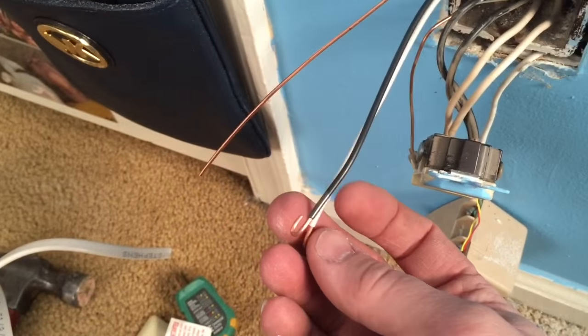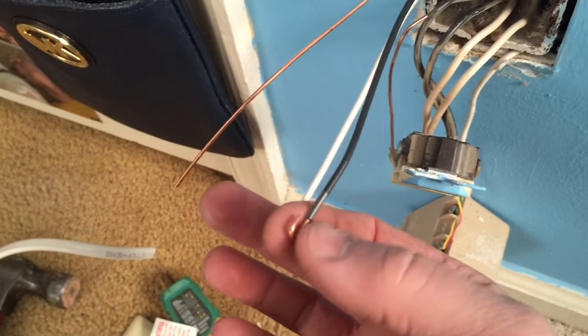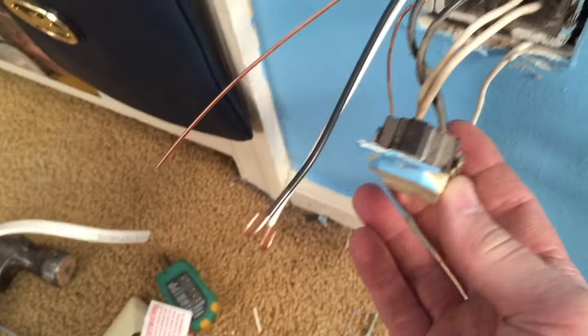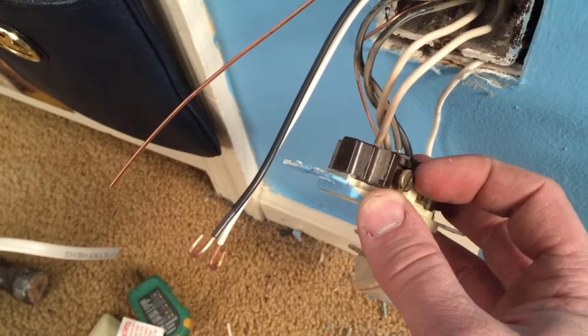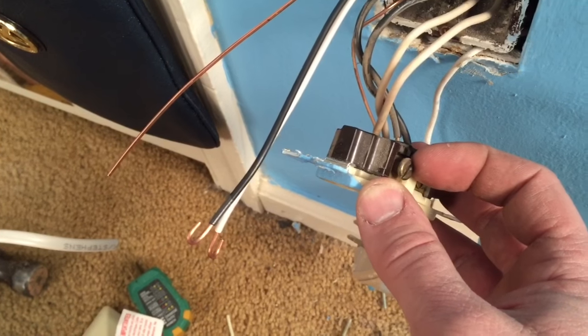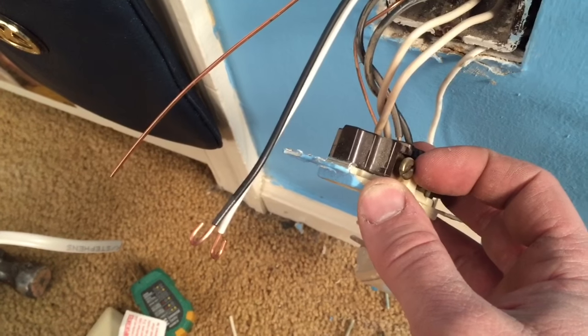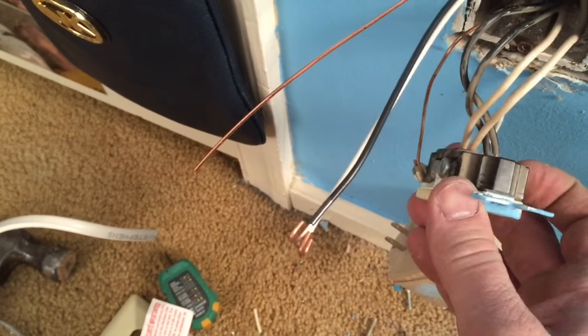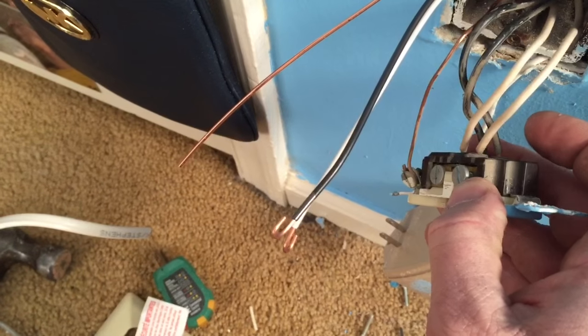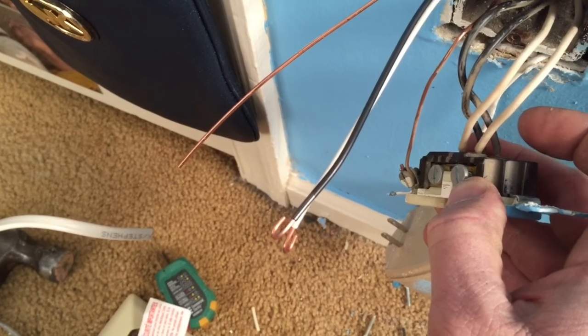Now here's our new wires, okay? I've already skinned them back and I've hooked a little hook on the end of it. The black wire we will be hooking on this side of the outlet, on the hot side. We'll just put it underneath that screw head right there, tighten it down. Neutral wire we will be hooking up right here on the other side where the other two neutral wires are hooked up.